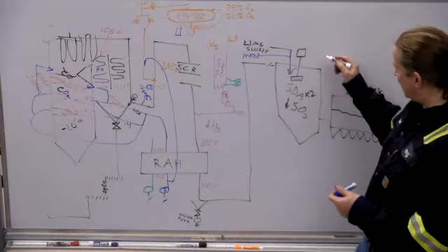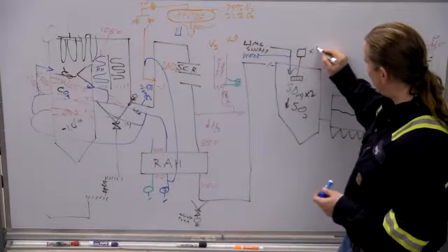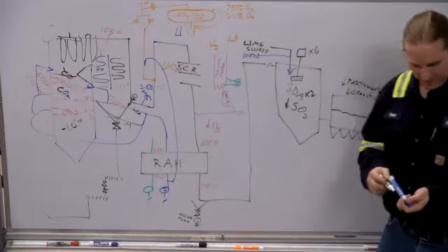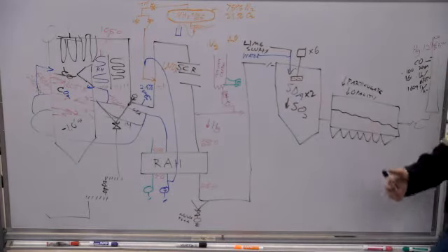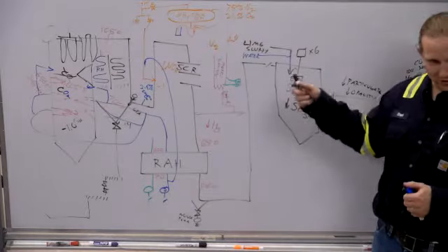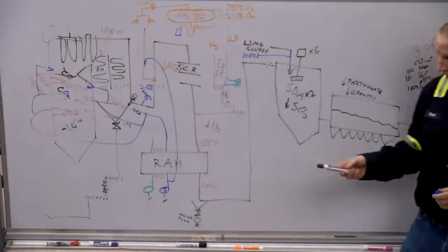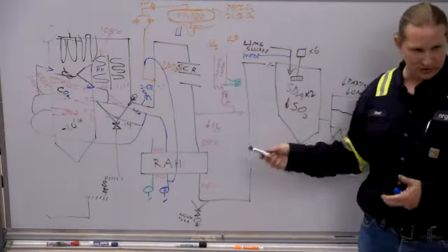There's two SDAs, and there's six atomizers, three on each SDA. Each one has an inlet duct. We take one out of service when we drop load. We can afford to take one out at full load if everything's working good.